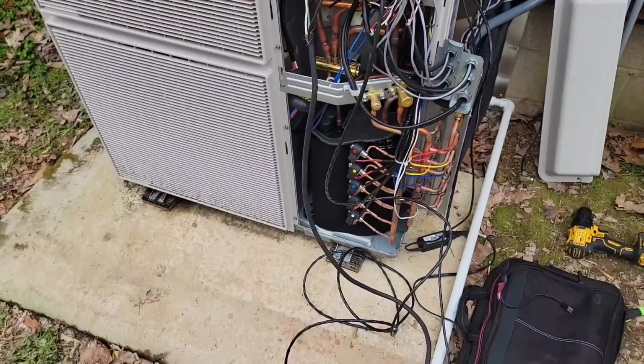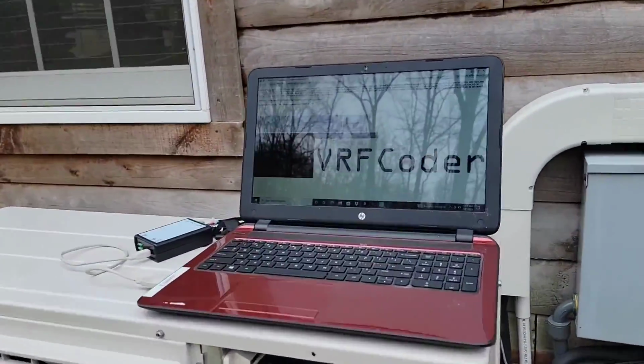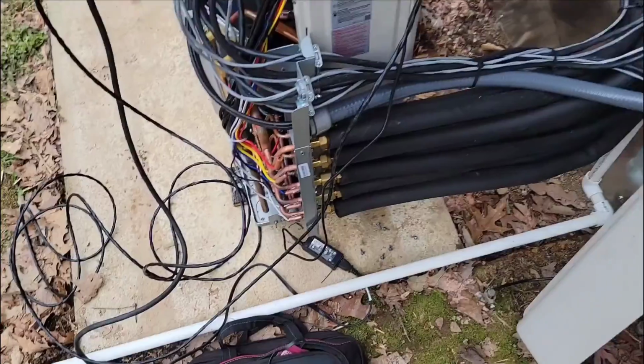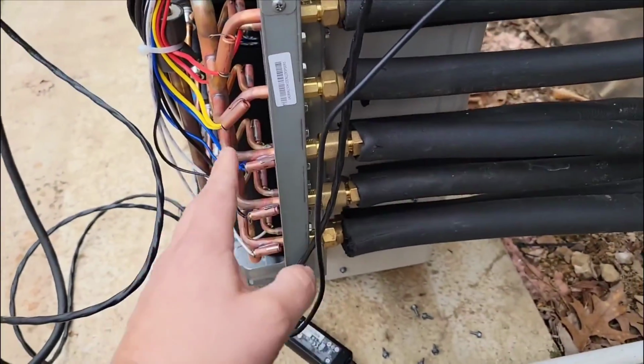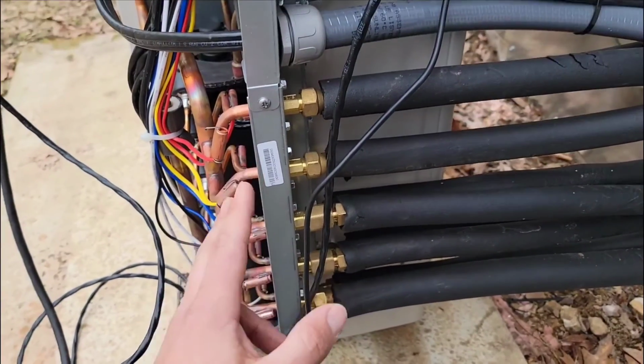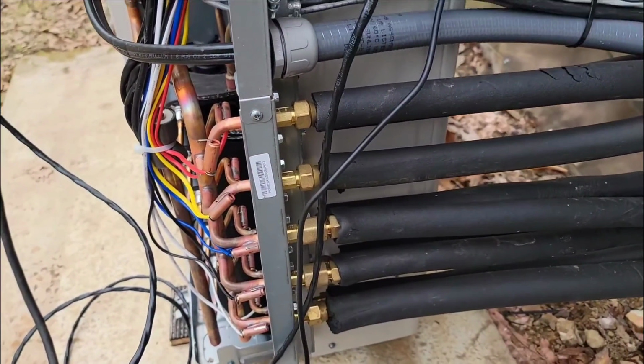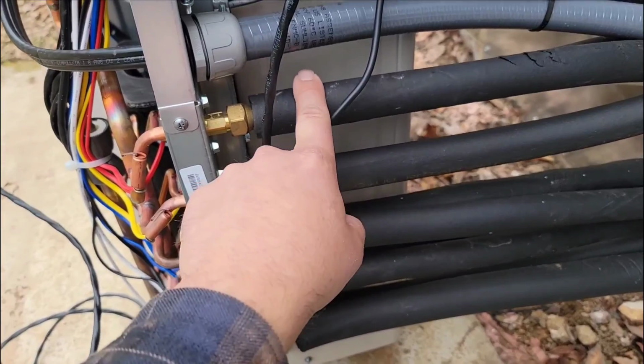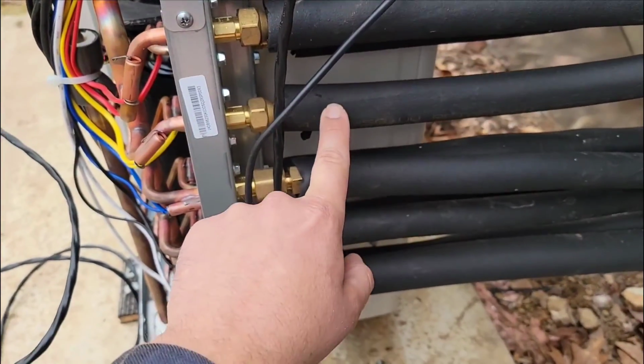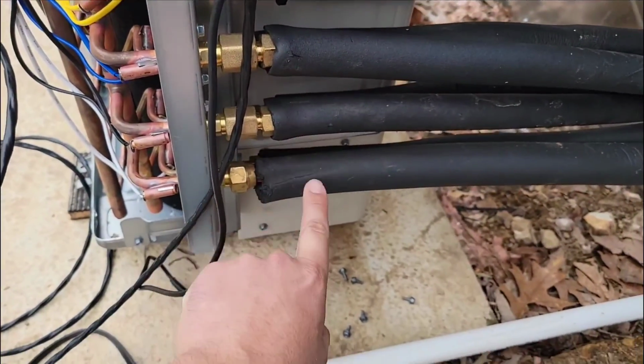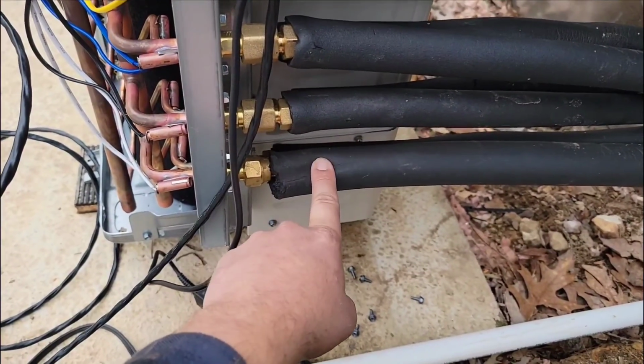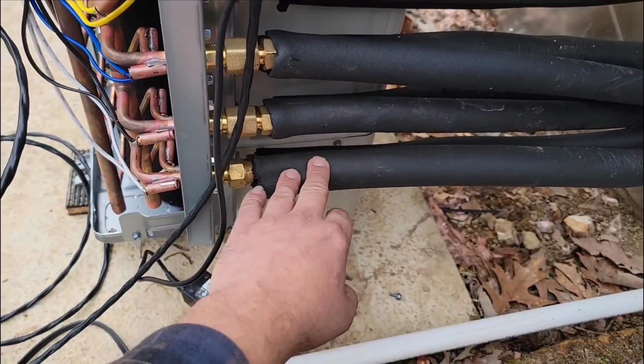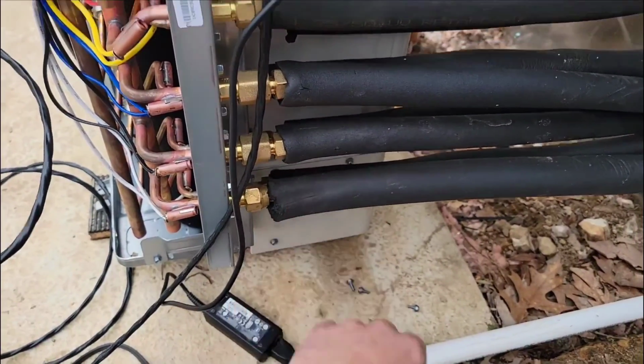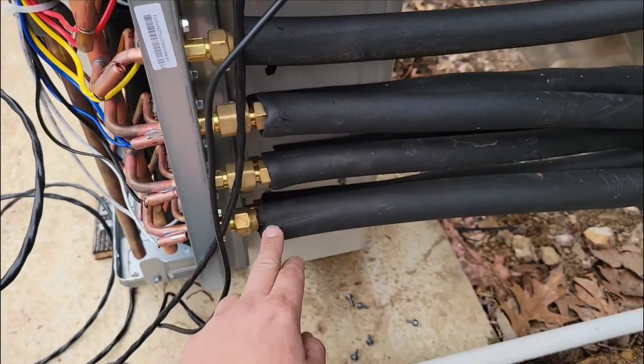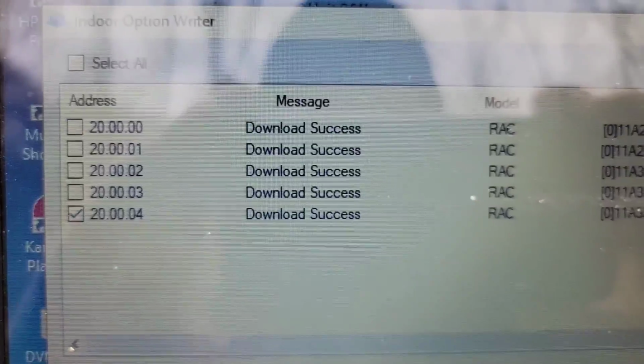Look at that VRF coder. Okay, no big deal, here we go. To do the option coding correctly, when you have more than one unit, you have to know which unit goes to which pipe connection. So for us, we did the 12 up here, the 7K, 7K, 7K, and then the 18 right here at the very bottom. We do the largest wall mount on the bottom, because our larger connections are on the bottom. So just a tip for you.